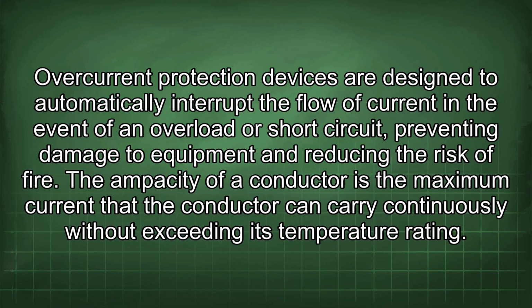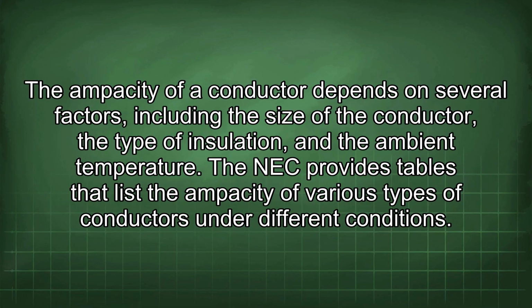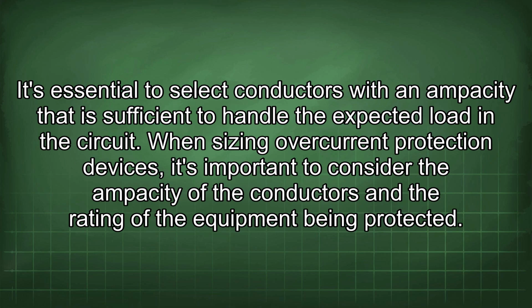The ampacity of a conductor is the maximum current that the conductor can carry continuously without exceeding its temperature rating. The ampacity of a conductor depends on several factors, including the size of the conductor, the type of insulation, and the ambient temperature. The NEC provides tables that list the ampacity of various types of conductors under different conditions. It's essential to select conductors with an ampacity that is sufficient to handle the expected load in the circuit.